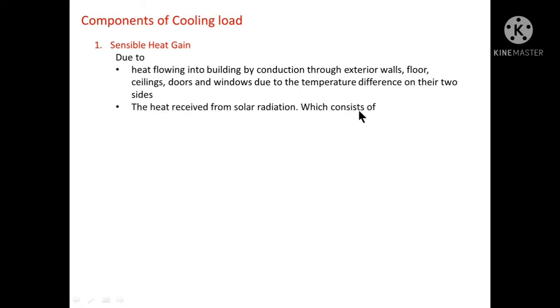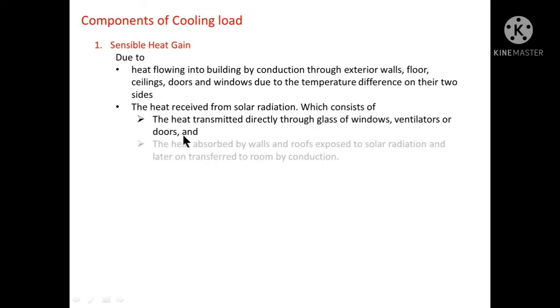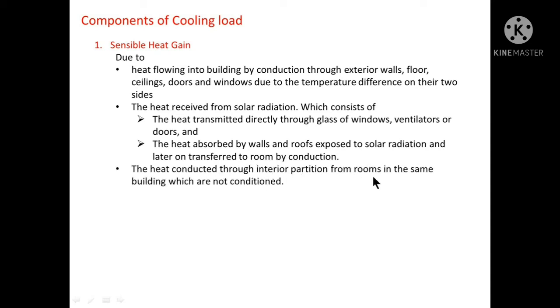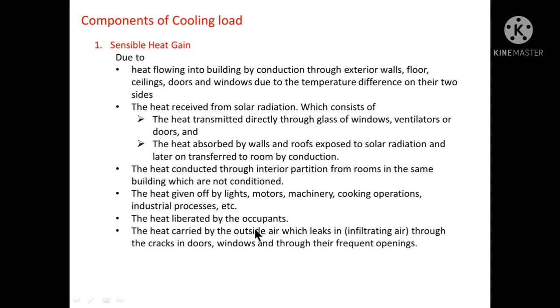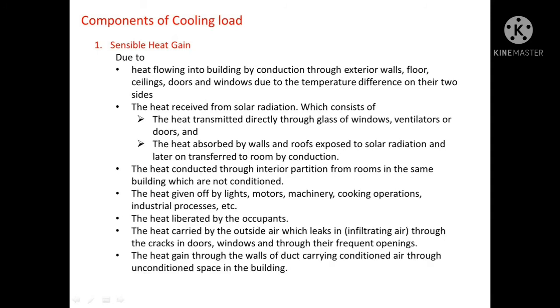The heat received from solar radiation consists of heat transmitted directly through the glass of windows, ventilators or doors, and heat absorbed by walls and roofs exposed to solar radiation and later transferred to the room by conduction. Next is heat conducted through interior partitions from rooms in the same building which are not conditioned. Next is heat given off by lights, motors, machinery, cooking operations, industrial processes, etc. Next is heat liberated by occupants. Next is heat carried by outside air leaking in through cracks, and heat gained through walls of ducts carrying conditioned air through unconditioned space.